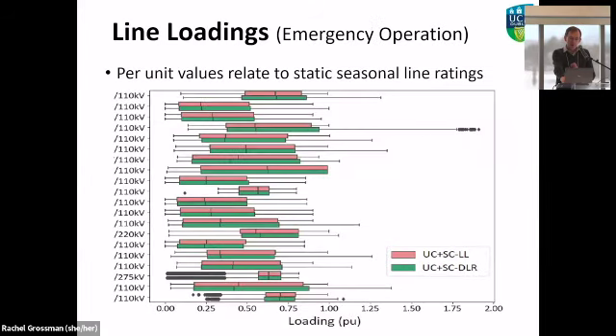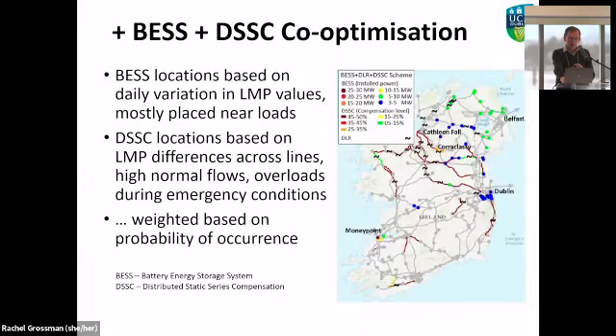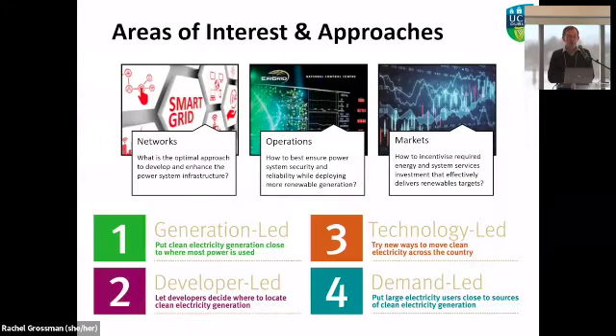So I'm going to switch to something slightly different. This is looking at the advantages of putting batteries in the system, because they can also help with local constraints, and power flow controllers or distributed static series compensation can also help. The nice thing about these measures is that they're short-term solutions. You implement them, they give you a solution. Sometime in the future, you upgrade your network, and then you can move these around the system to where the network is now constrained.